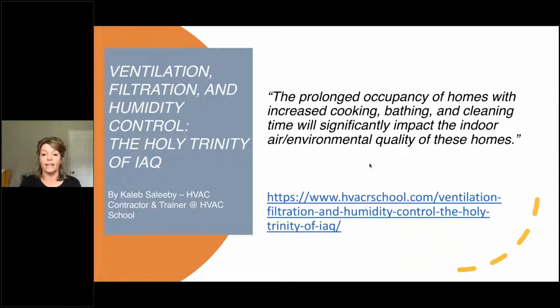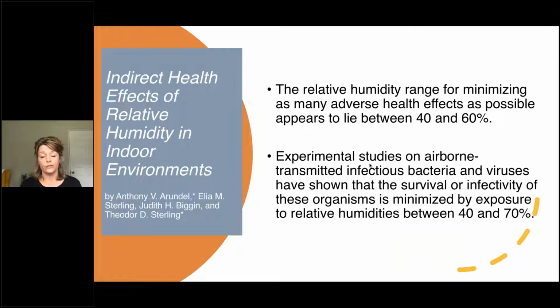So it's a really great article, I highly recommend it. There's a lot of research out there on the effects of relative humidity on our health. Right now we're hearing a lot with COVID about 40 to 70% relative humidity. I caution against just going by relative humidity because it's all relative to temperature. If somebody is chasing 70% relative humidity in the wintertime, they're going to be in a world of trouble trying to dump that much moisture into their air in Wisconsin, Minnesota, or Michigan. And 70%, even in summertime, is pretty high compared to the recommendations we'll see here.